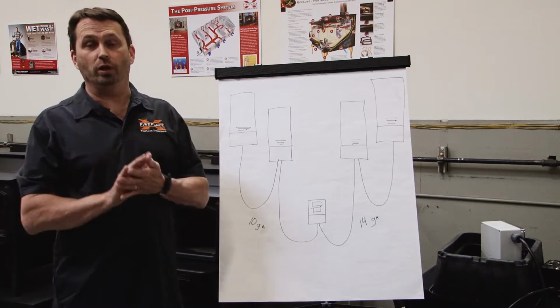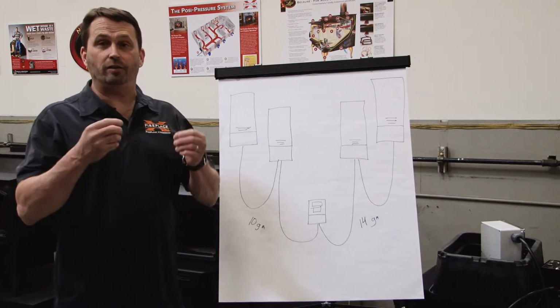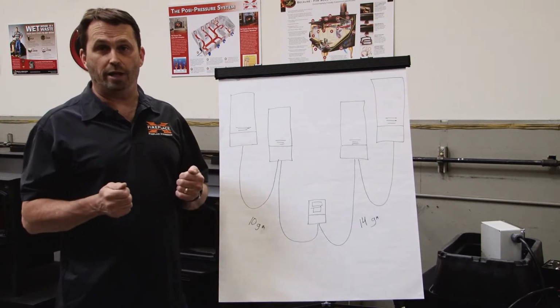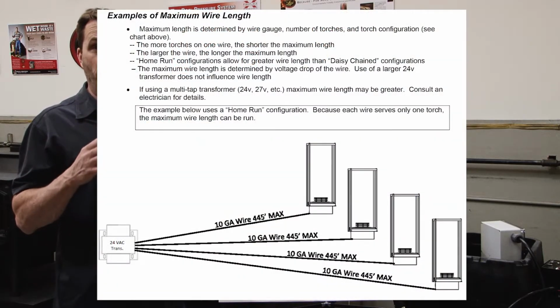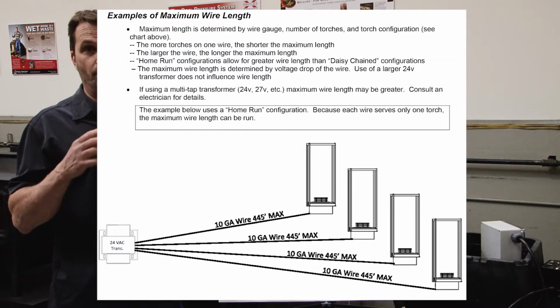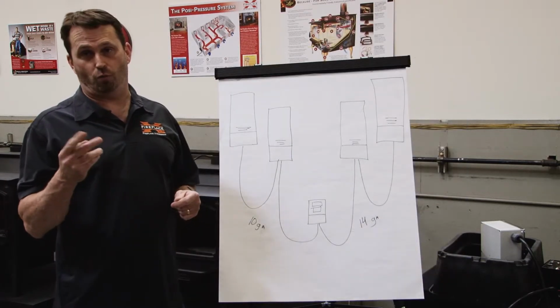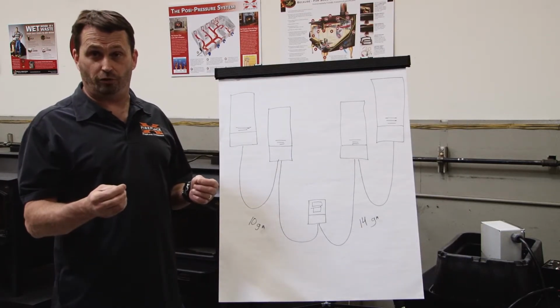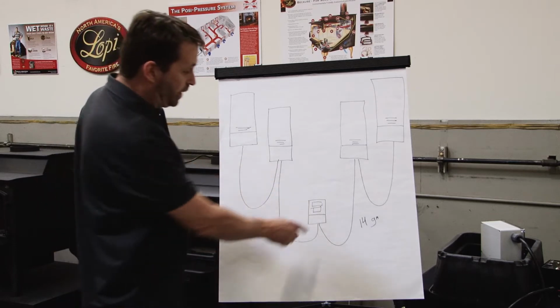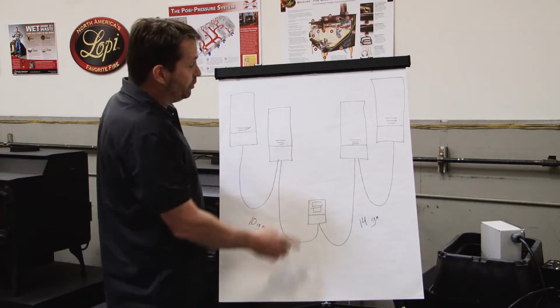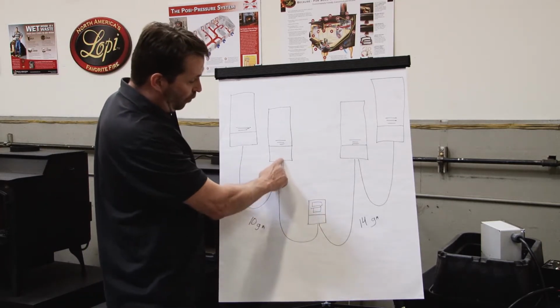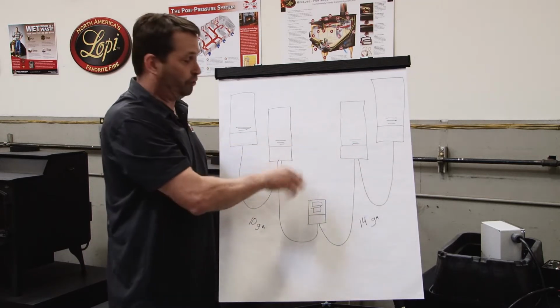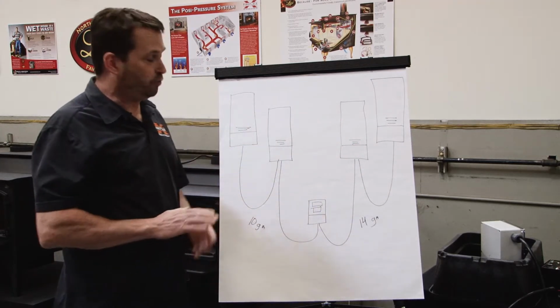This is really critical, so take the time to look in the installation manual and look at the wiring diagram chart that we provided. There are 2 ways you can run wires from your transformers out to your torch. Pardon my drawing, but this is our transformer, and this is 24 volt service out to each of the torches. So remember, 4 torches per transformer.